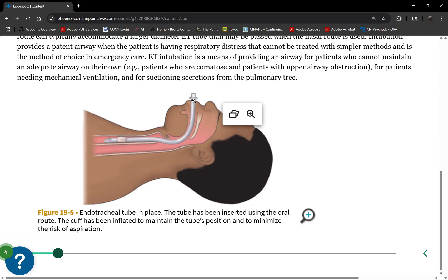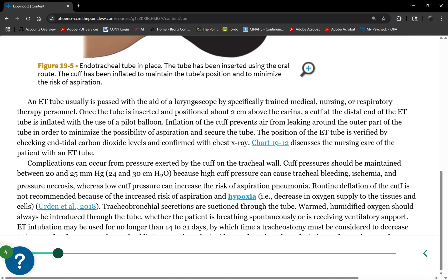If there's air in the pilot balloon, that means the cuff is inflated. If the pilot balloon is flat, that means the cuff is flat. So that's your indicator of whether or not the cuff is inflated. But of course, the pilot balloon cannot tell you how much pressure is in there. So you have to attach a manometer, a pressure measuring device, onto the pilot balloon and press the trigger and it will read. What do we want the reading to be? Between 20 and 25, what? Millimeters of mercury, or 24 and 30 centimeters of water.